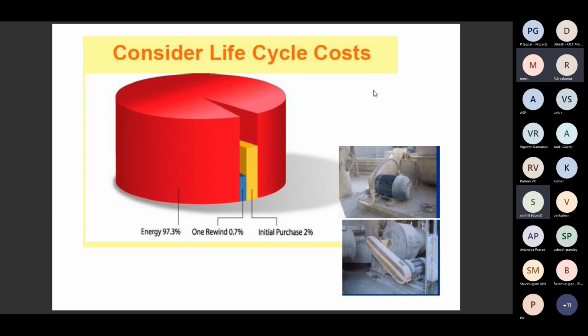So this is the life cycle cost. It is applicable not only to motors, but also to air compressors and any energy consuming equipment. The life cycle cost is very important. Out of this 100%, the energy cost is here. This graph says 97.3, but normally it is almost 90 to 93% of the whole life cycle cost that goes to energy alone. 2 to 3% is for the initial investment cost, and the remaining is the maintenance cost. So the major area is energy, so based on the application and requirement, the unit can decide to go with the energy efficient motor. Very, very important. Next.